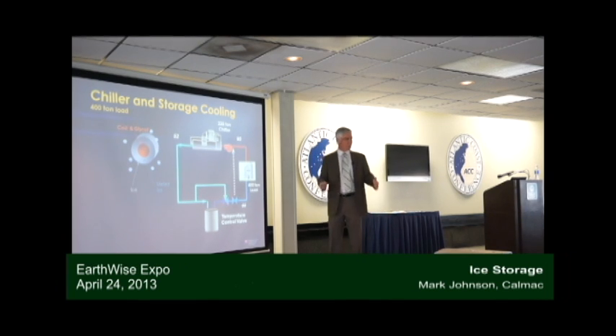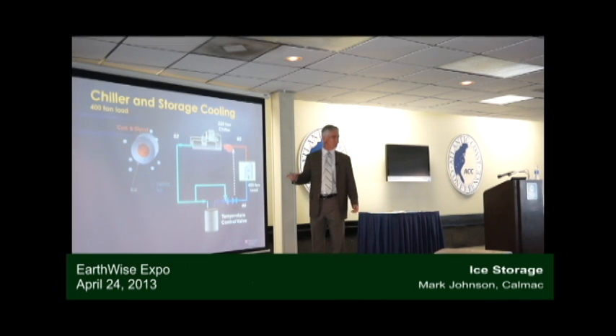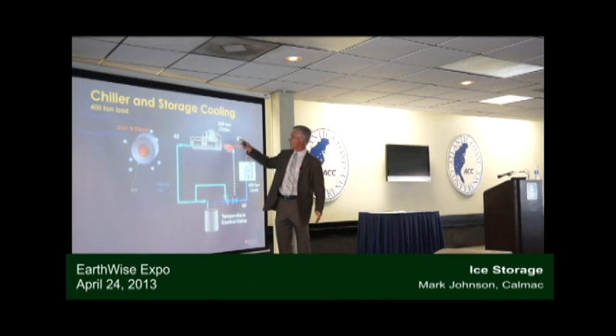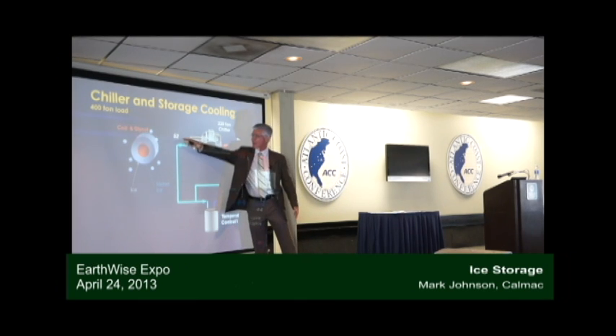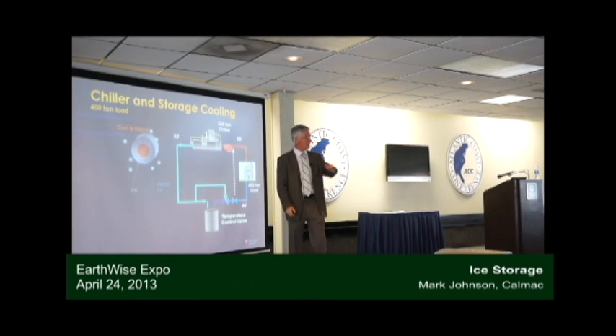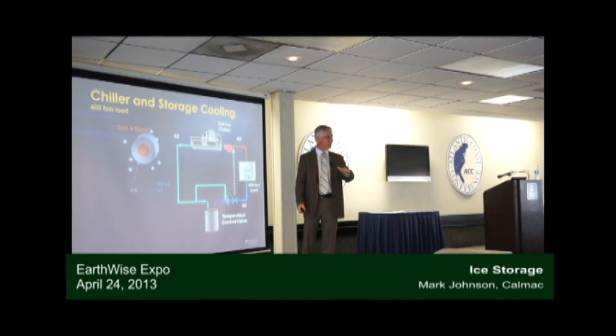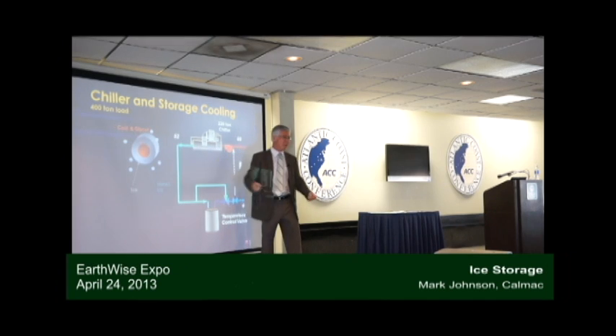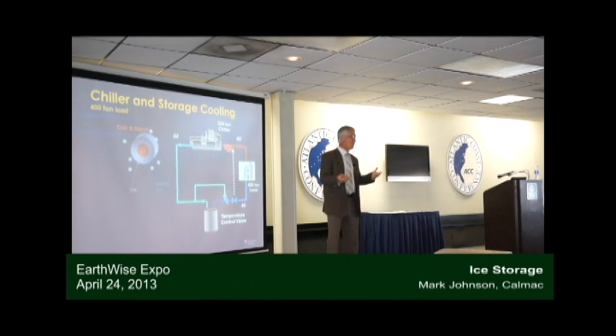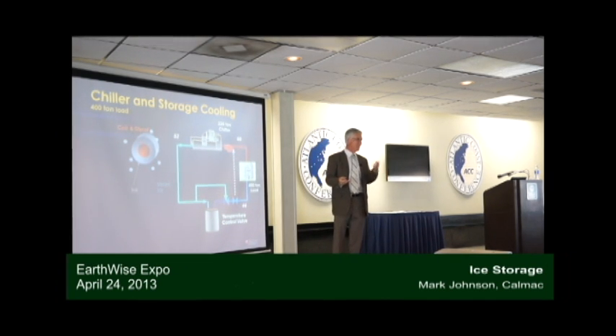Okay. Any engineers, design engineers, mechanical engineers in the crowd? There's one. This chiller operating at 52 degree leaving temperature in the peak of the day versus that chiller operating at a 44 degree leaving temperature. What do we know about that chiller's performance at 52 versus 44?